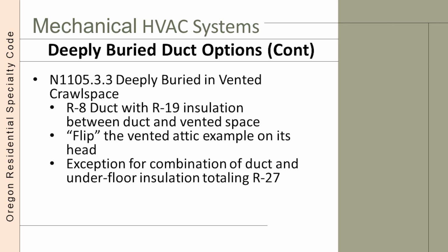Under section N1105.3.3, the duct is located in a vented crawl space. The easiest way to think about this application is that it's just a vented attic flipped upside down. R8 insulated ducts must be buried with at least R19 additional insulation between the duct and the vented crawl space. And just like the vented attic, there is an exception allowing for any combination of duct and floor insulation as long as the total insulation between the duct surface and the vented space is at least R27. And of course, two additional measures must be selected.